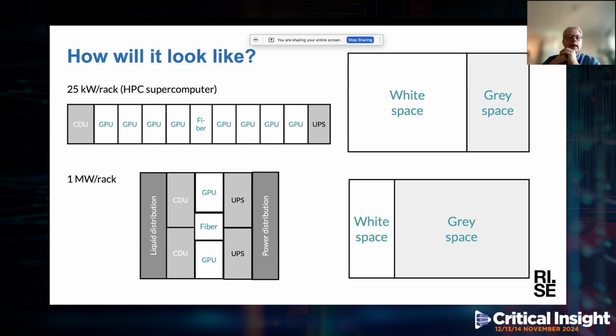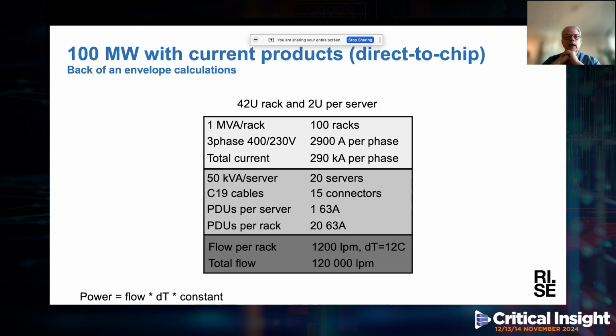So the 25 kilowatt per rack row on the upper side is the one I showed you, and the 1 megawatt rack is the ChatGPT picture I showed you as well. Then I took these numbers and tried to think, okay, if we would do it with current products, what would happen? If you look at this table, you'll find out that you need 20 63-amp PDU strips, and you'd have to fill the whole outside of a rack with just PDUs if you used today's technology. And you need a pump per rack that does 1200 liters per minute.